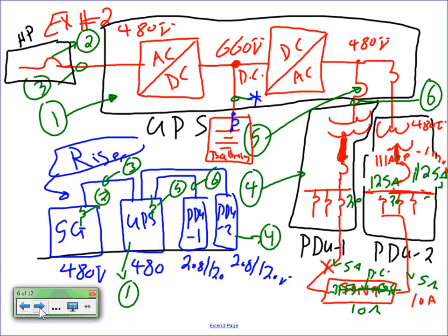There will be 20 amp branch circuits, and in this case, what did we say the PDU is, 40? It's like a transformer. If you take 40 kVA, what's the full load current on the 208 transformer? We were there a second ago, guys. 7-7, right? Can you go to 7-7, please? Okay, so if I have 40, I don't have 40, so I have 45, say. Most likely it's going to be like a 100 amp panel coming out of it, close to 100 amp, 125 amp panel tied to it.